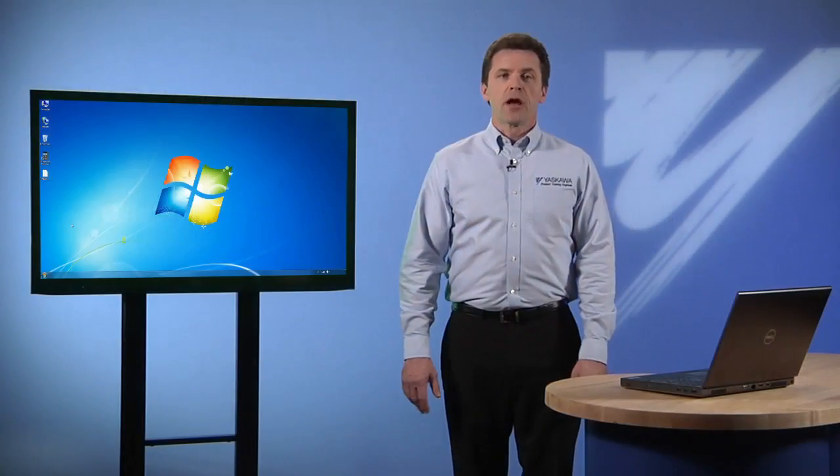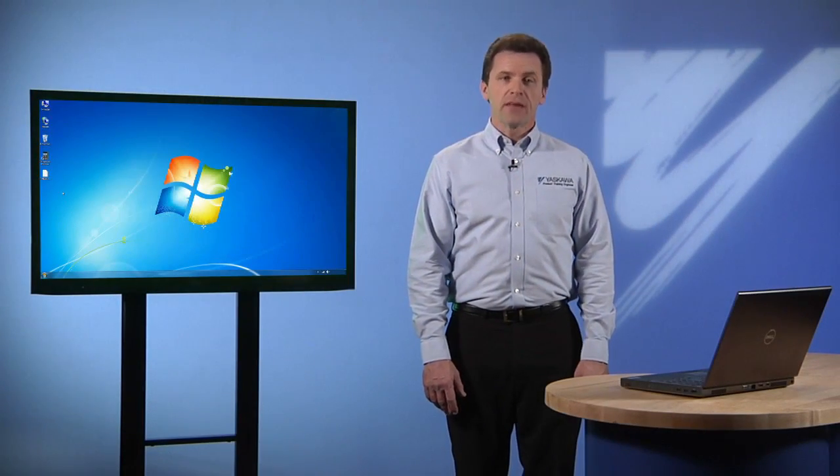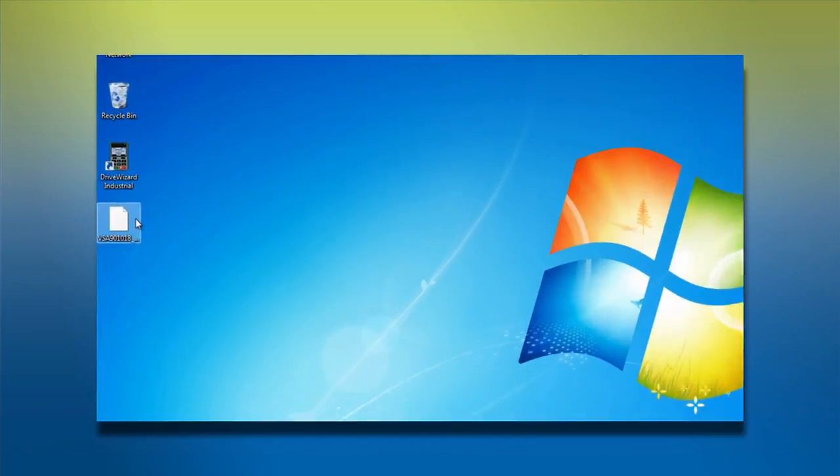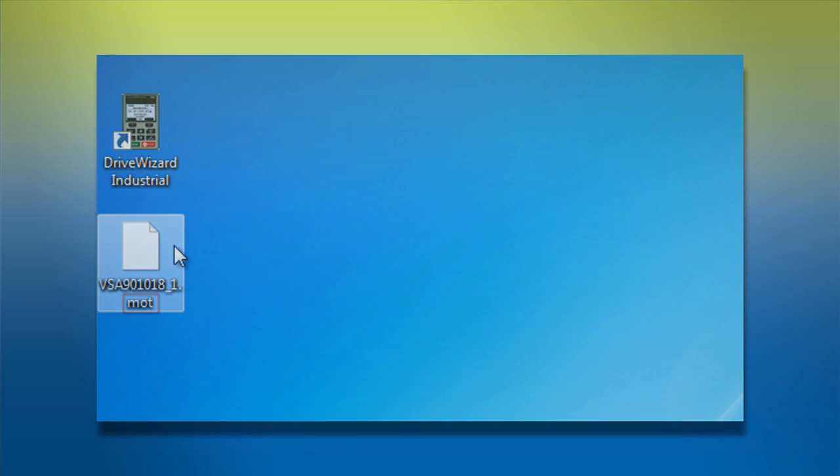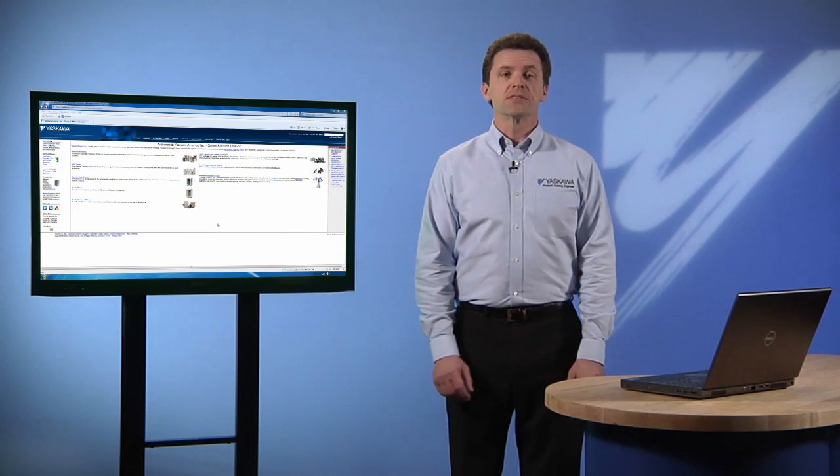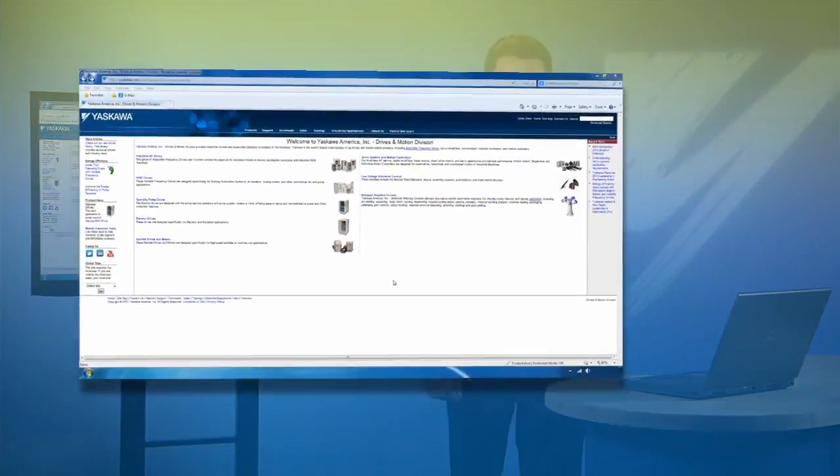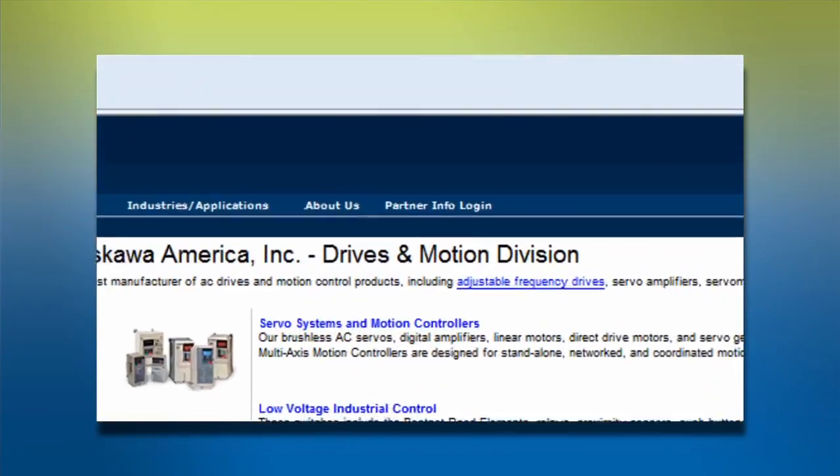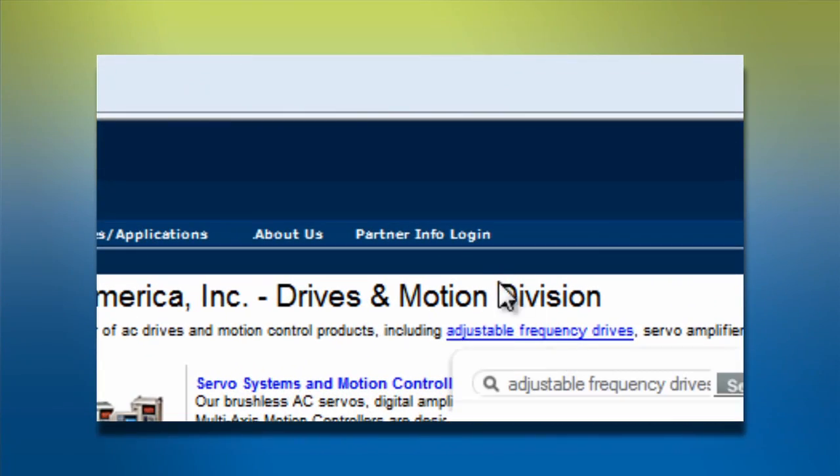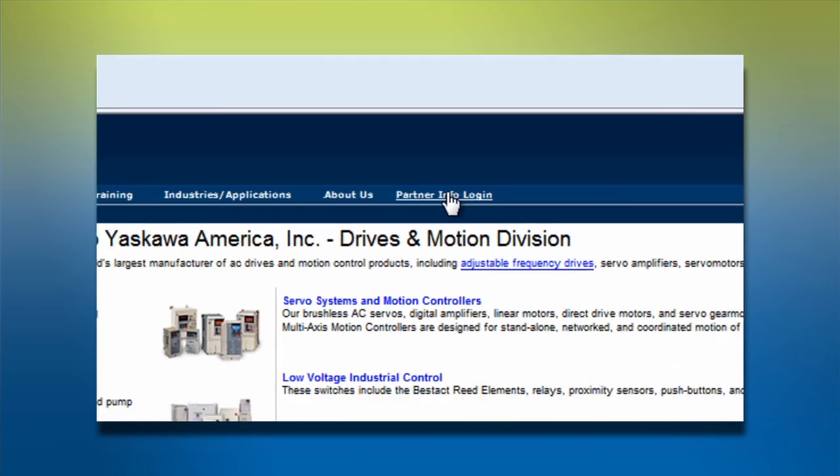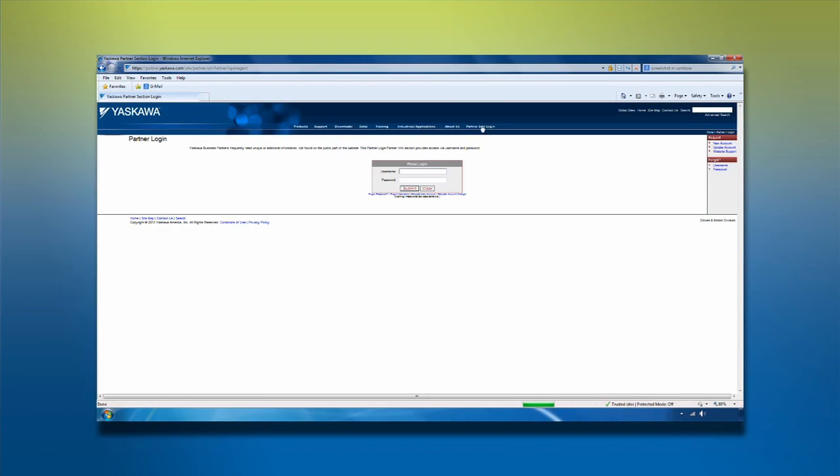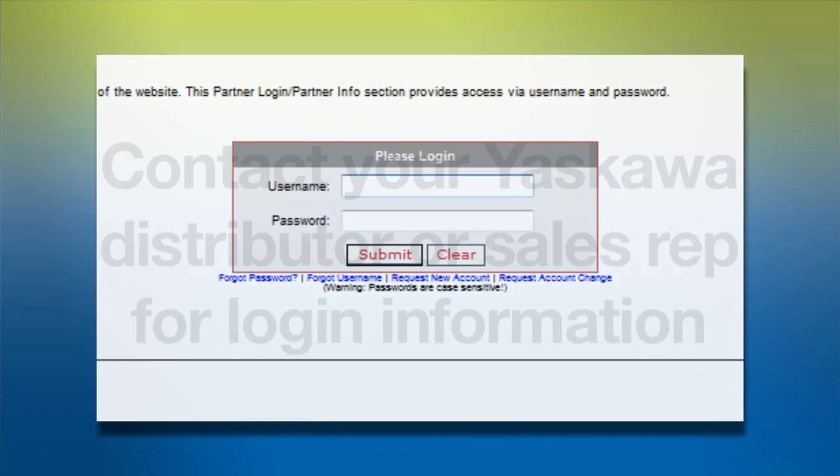Now begin the process by obtaining the latest version flash file for your drive. For 1000 series industrial drives, these files will have the file name extension .mot. Yaskawa posts these files on the web for your convenience. The link for the Yaskawa Partner Login Web Portal is in the top menu at yaskawa.com. The username and password you'll need to gain access is available by contacting your local Yaskawa distributor or sales rep.